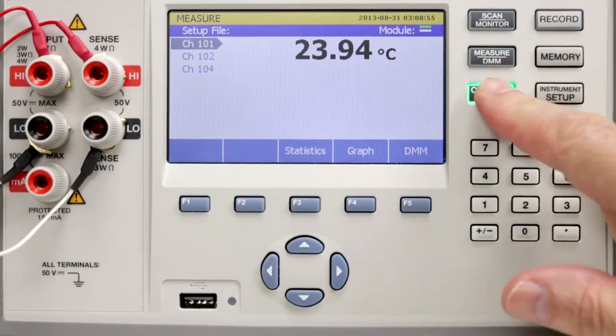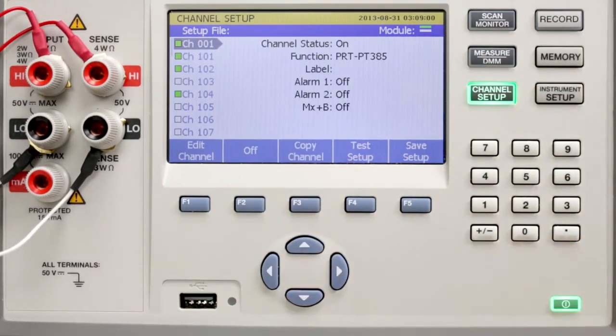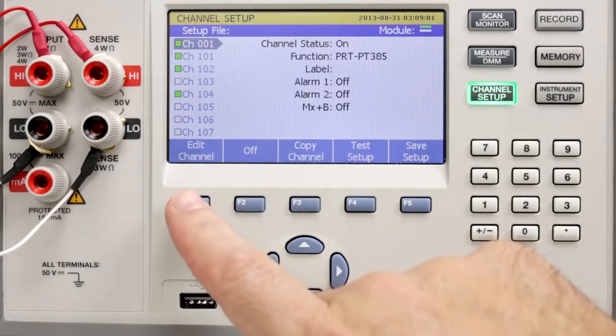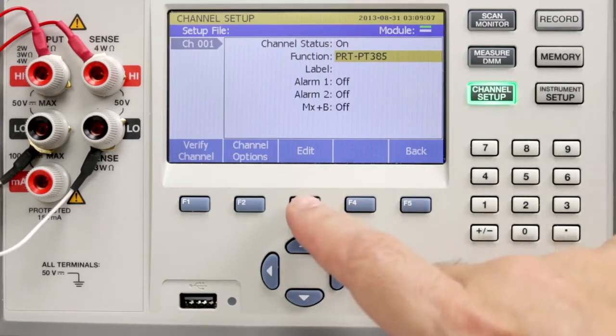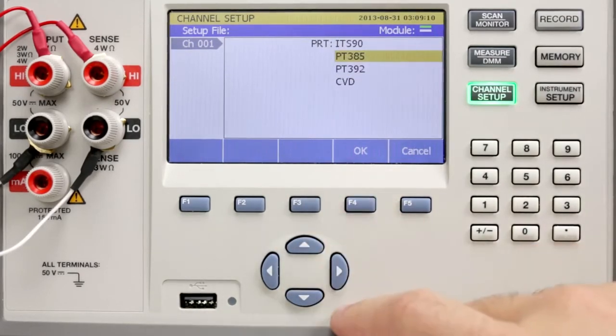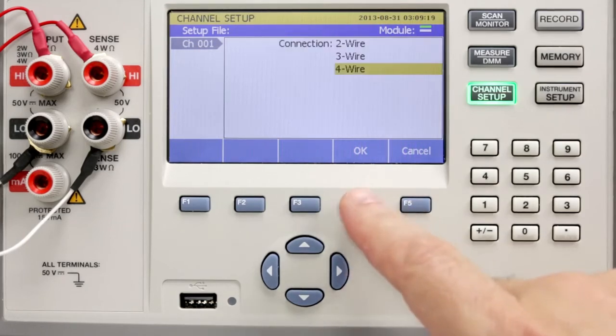Press channel setup. Set channel 1 to on. Select edit channel. Set function to PRT. We'll choose PRT PT385. Set the resistance value to 100 ohms and choose 4-wire PRT.